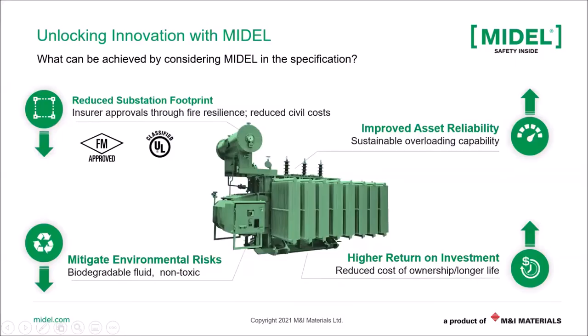So let's look at what are the advantages of the chemistry of these MIDEL fluids that allow them to be used so differently than the standard approach with mineral oil and transformers. First of all, the biggest difference is that because they're FM approved and UL classified liquids, you can use them differently. You can use them in closer proximity to buildings and people. And we're going to go into detail on that.